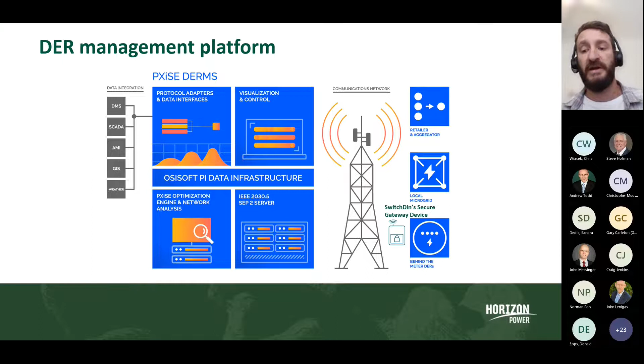Control hierarchy was really a significant part of the planning process for building this DER technology stream. So I thought it's just important to highlight how we approach this from a primary, secondary and tertiary layer of control. Primary at the milliseconds, secondary at the seconds, and tertiary at the sort of minute dispatch scale. In the traditional stream in the middle there, we have at the primary level, the power station asset controllers. So this is your generator governors and AVRs. It could be your transformer AVRs, and also the inherent inertia of the system, right?